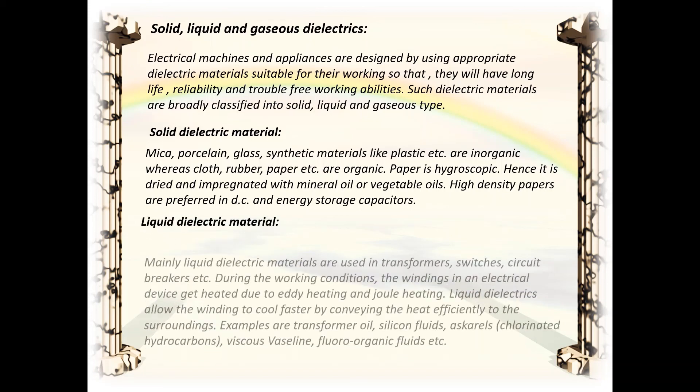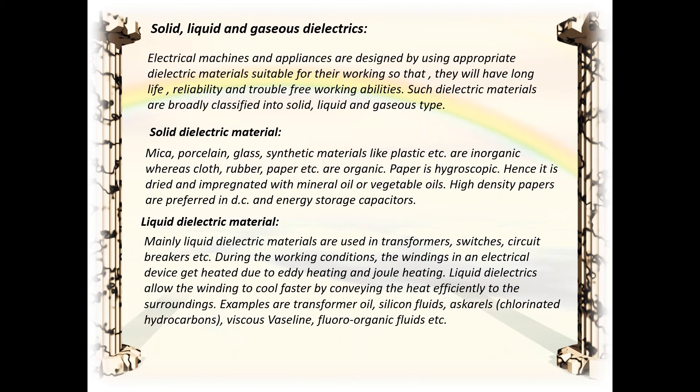Liquid dielectric materials are mainly used in transformers, switches, and circuit breakers. During working conditions, windings in electrical devices get heated due to dielectric heating and Joule heating. Liquid dielectrics allow windings to cool faster by conveying heat efficiently to the surroundings. Examples are transformer oils, silicon fluids, chlorinated hydrocarbons, viscous vaseline, and fluoro-organic fluids.